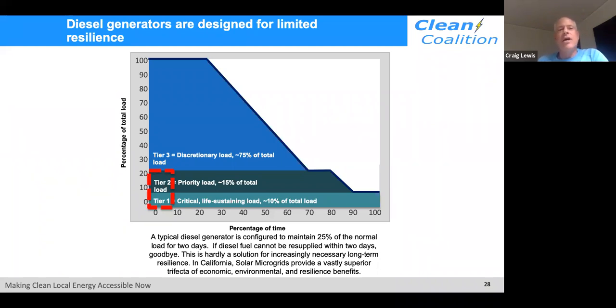I want to contrast that with the resilience from a diesel generator, which most people think of as the default solution. Compared to a solar microgrid, a diesel generator is not resilient at all—that little red hatched rectangle is the resilience you get from it. A typical diesel generator has 2 days of on-site fuel supply, keeping tier 1 and tier 2 loads on for 2 days. After that, your lights are out. Most facilities won't be able to resupply diesel fuel in an emergency—it'll go to top priority critical community facilities, and everybody else will be lights out.